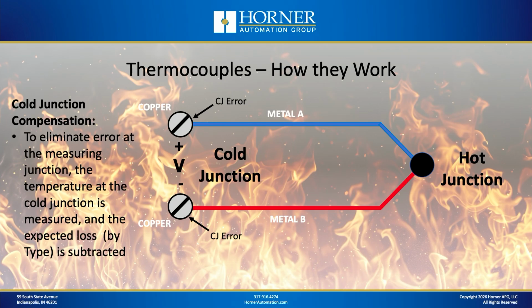So any measuring instrument which is dealing with thermocouples has to handle something called cold junction compensation. Basically, it has to have a way of subtracting out that CJ error I'm showing there on the screen. The way that is done is that an additional temperature sensor that's part of the measuring instrument will measure the temperature at the cold junction. Then, based on the type of thermocouple that's connected, it will predict what that voltage loss will be. It will subtract off that voltage loss, and the result will be a reading that reflects the hot junction only.